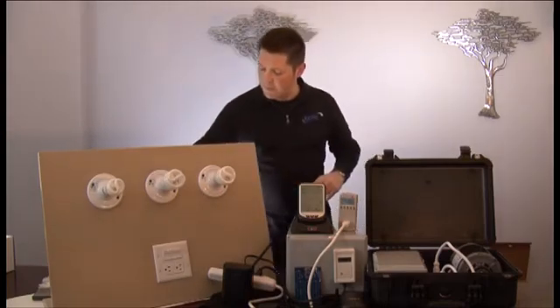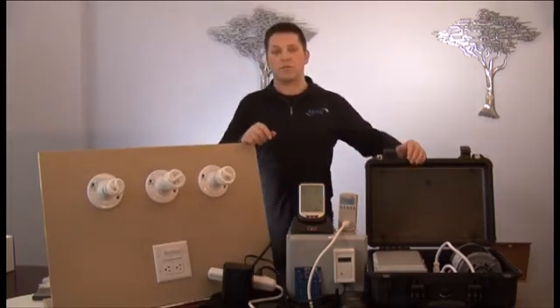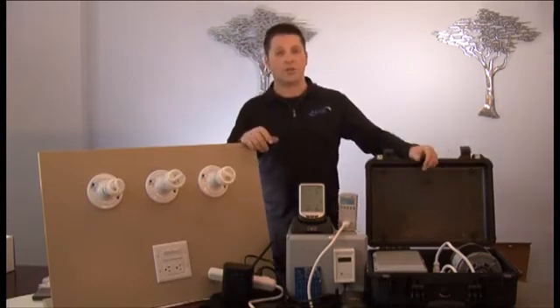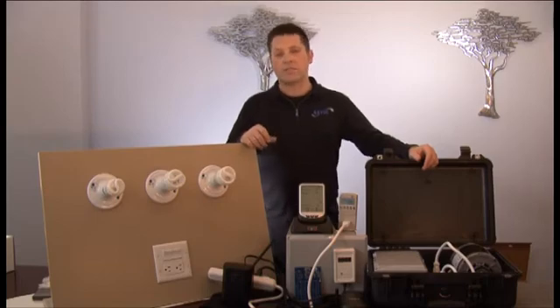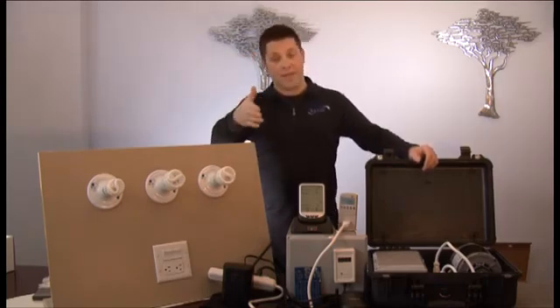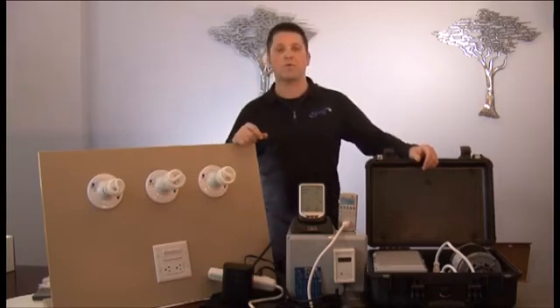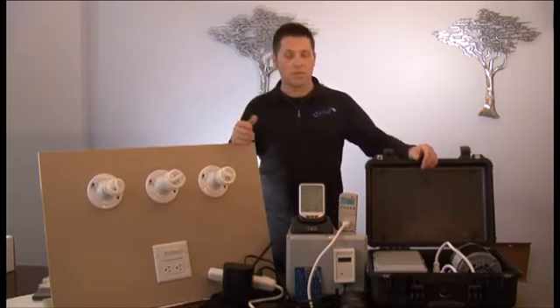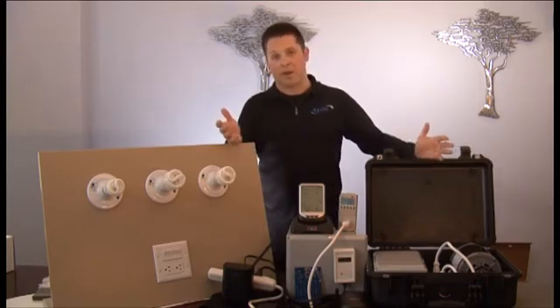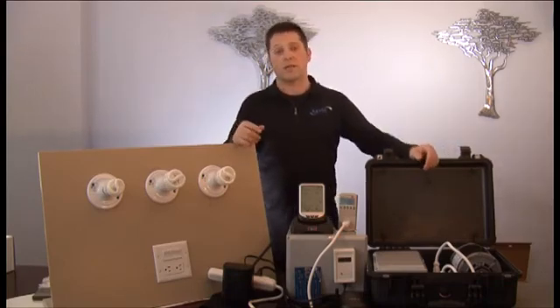This type of product is often used in factories, wherever you have a motor, air conditioner, etc. What a capacitor can do by leading voltage is improve the power factor from, let's say, 70 to 90, just for an example, so you can reduce the amps needed by 20%. So if you have an air conditioner, let's say at an 80 power factor using 5 amps, by power factor correcting it, you can reduce those amps to 4.